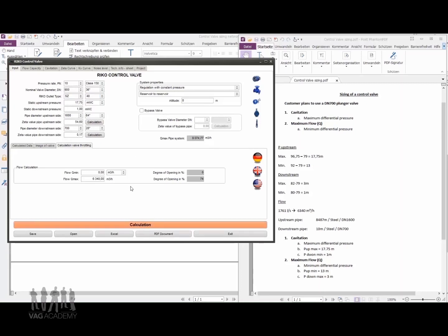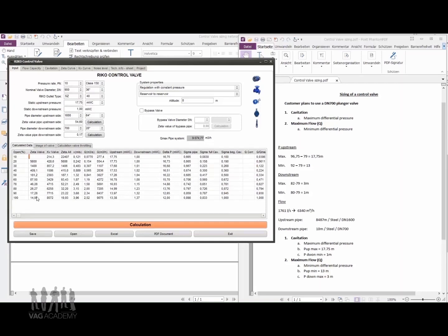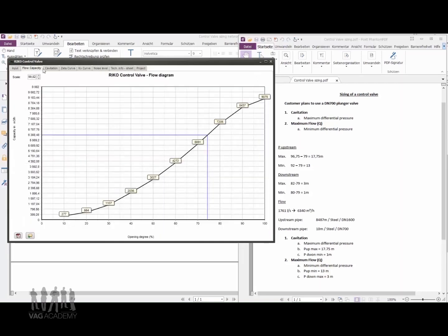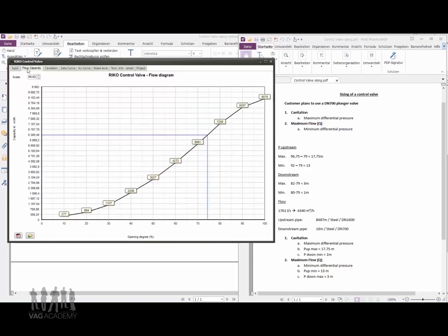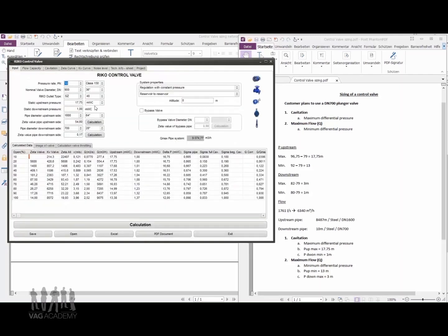I can see that I meet my flow requirements and there are no yellow values. Looking at the flow and cavitation chart, I have no cavitation, though I'm fairly close. So I now have a valve that fulfills point number one — cavitation-free operation. We're sizing here for a flow that may happen in about 30 years, but it's the maximum requirement.